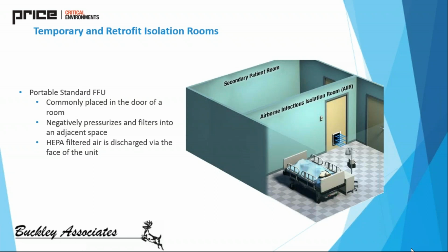And then lastly, the last configuration here, we see a standard supply air FFU, and it can be placed right into the door of one of these facilities. So we've already started to see this application in a lot of hotel rooms that are being converted. What they're doing is taking this fan filter unit, putting it right into the doorway, sealing off the other cracks, and then HEPA filtering and exhausting that air into some other space. So this is the easiest conversion we've seen for either dorms or hospitals. This is the unit that they've been using for those specific applications.